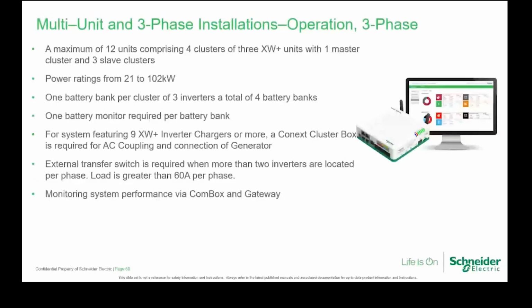In a three-phase installation, you get a maximum of 12 units, comprising four clusters of three XW Plus units or XW Pro, with one master cluster and three slave clusters. So you can go from 21 kilowatts up to 102 kilowatts. You can use one battery bank per cluster of three inverters and a total of four battery banks. One battery monitor is required per battery bank. For systems featuring nine XW Plus inverter chargers or more, a Conext cluster box is required for AC coupling and connection of the generator. The AC Conext cluster box is covered in the multi-unit planning guide and the multi-unit design guide.